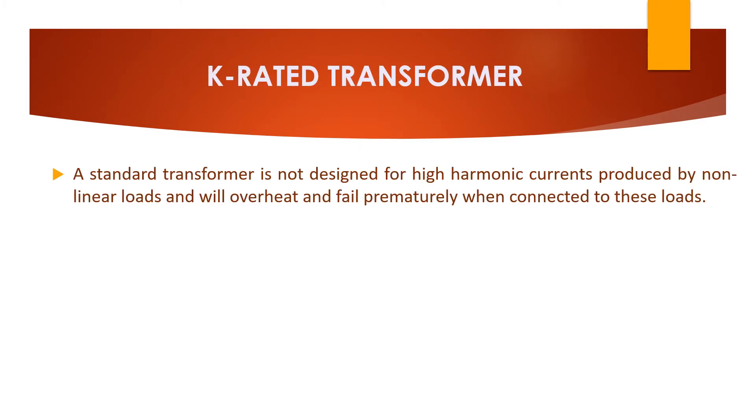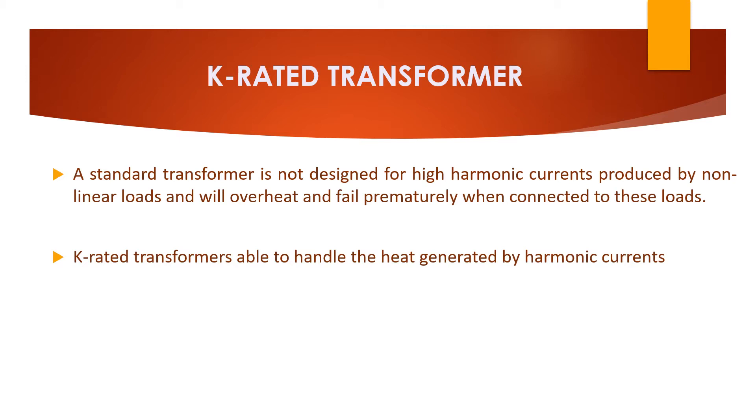K-rated transformer is different from standard transformer because standard transformer is not designed to handle high harmonic currents, which in turn produces high heat. So that normal transformer fails to handle these kinds of non-linear loads. So then what is K-rated transformer? K-rated transformer is able to handle the heat generated by harmonic currents or non-linear loads.